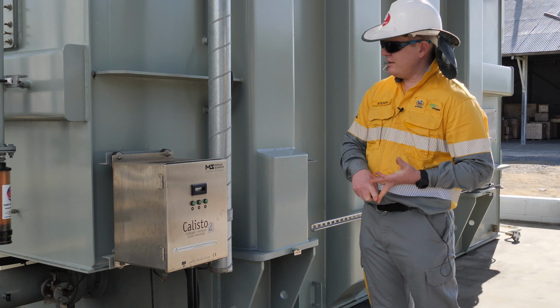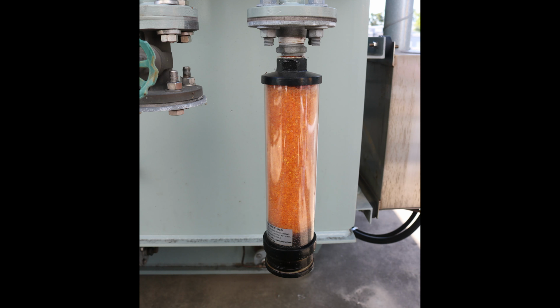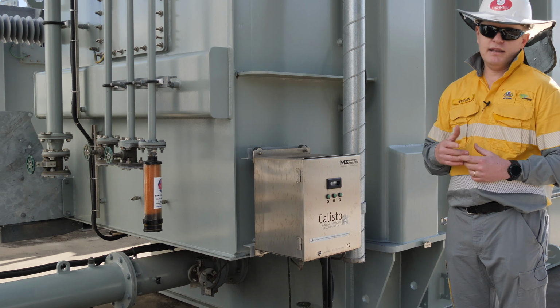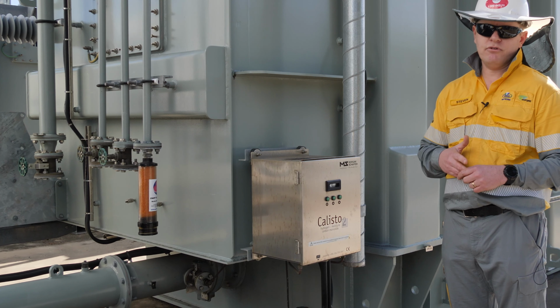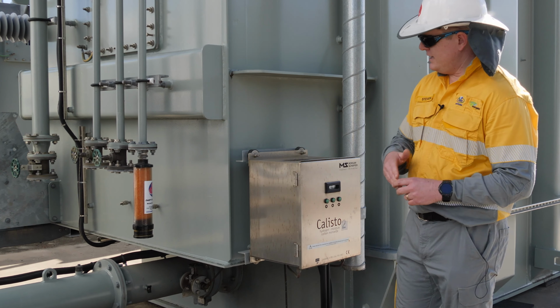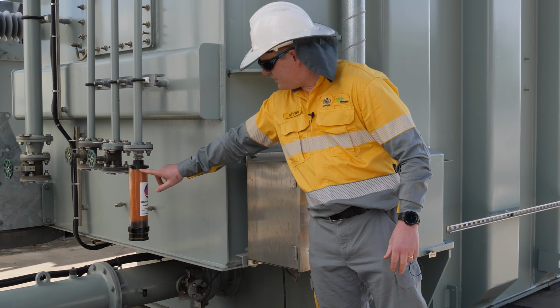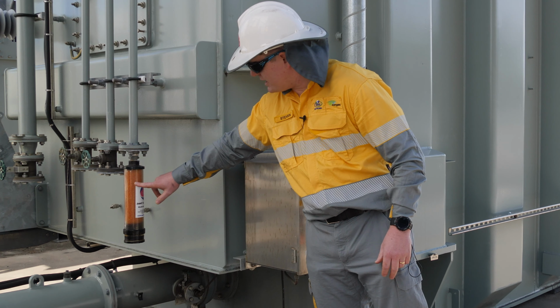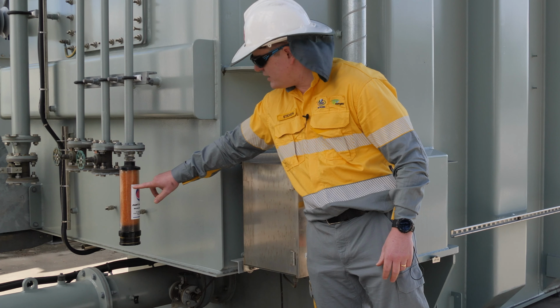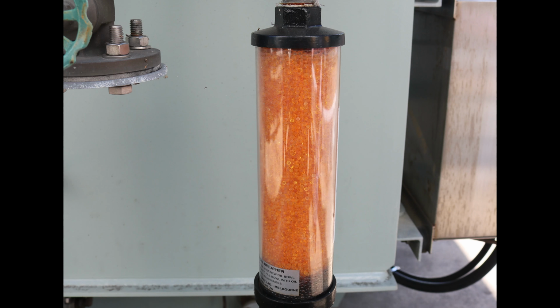The third feature I'll point out on this side is a silica gel breather. As I mentioned, moisture is really bad for power transformers, and what the silica gel breather does is, in a free breathing transformer, the air will pass through it and the breather will extract any moisture from the air. These breathers are made up of silica gel beads, and they will change colour when they've absorbed all the moisture they can. And this breather has turned to an orangey reddy colour, which means that it's full of moisture and needs to be changed.